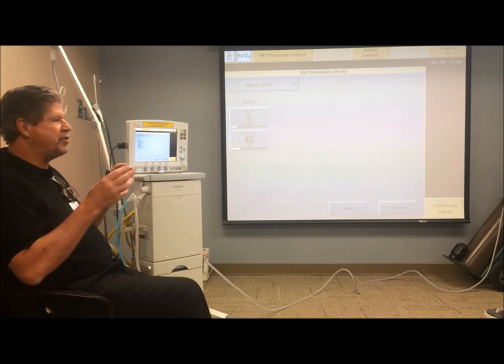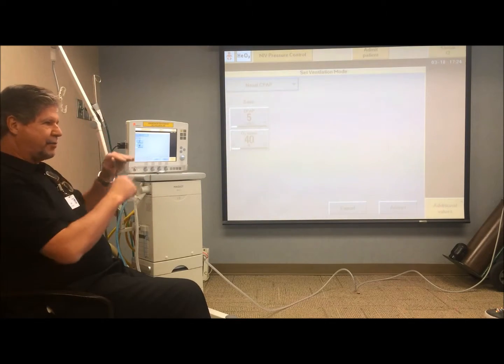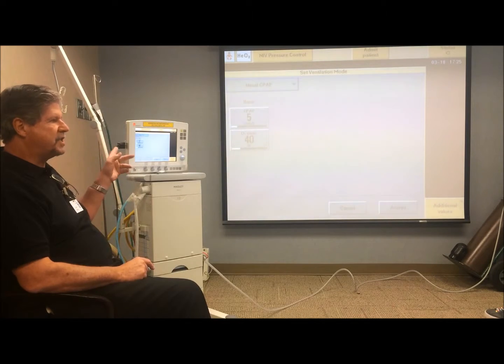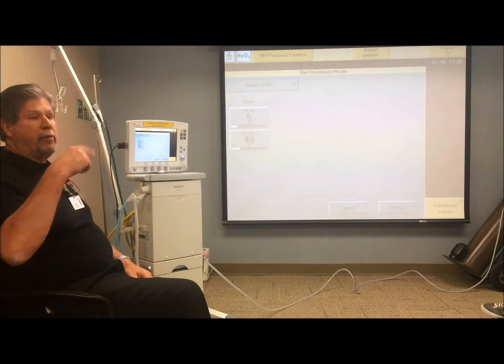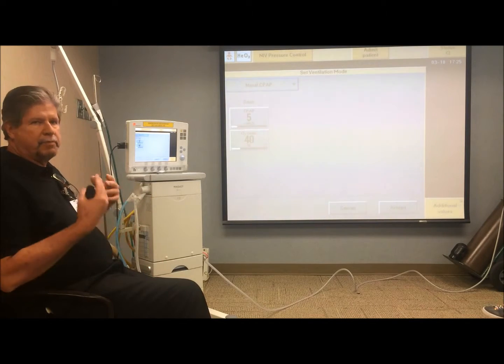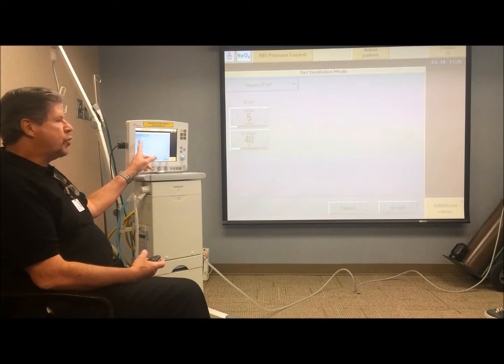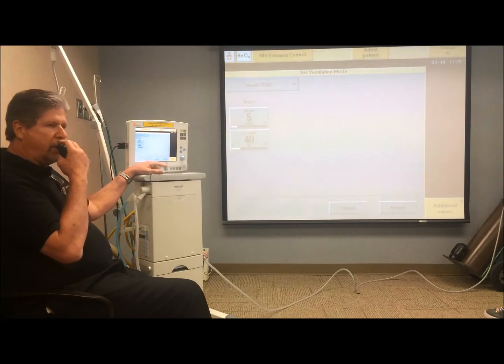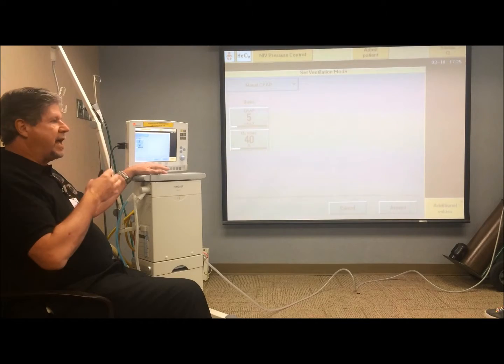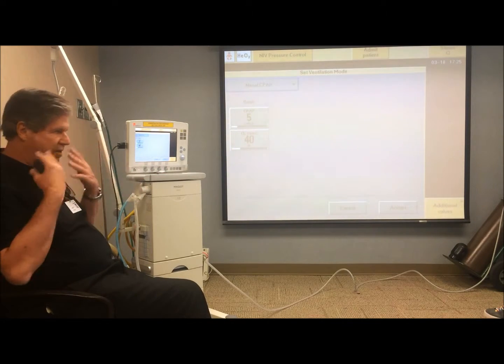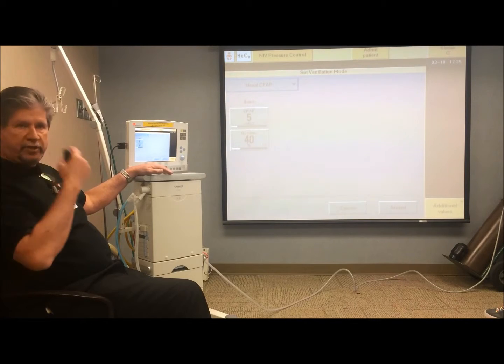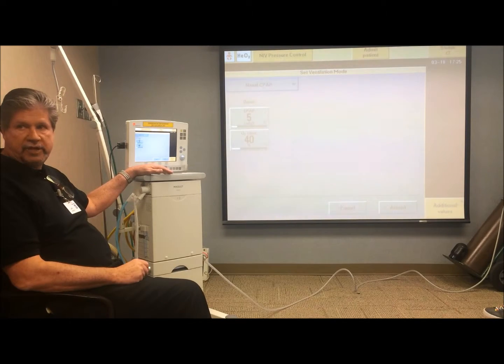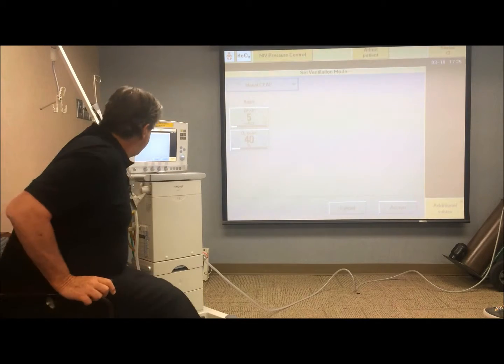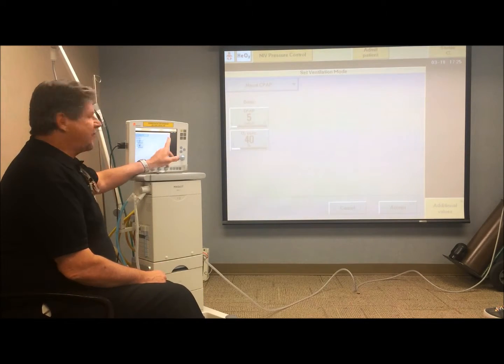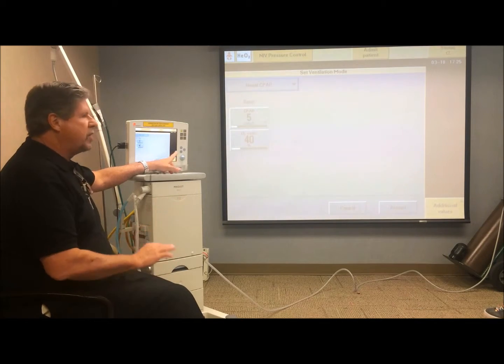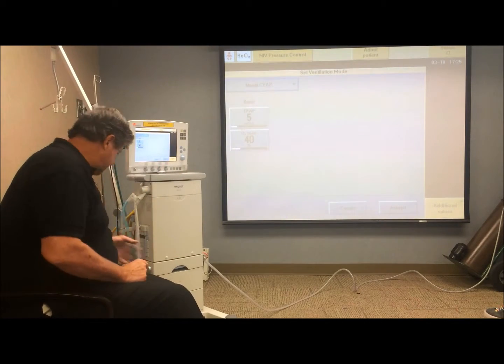It's pure CPAP as compared to using a device with a manometer and setting up a little PEEP column and all that. You know that you have an accurate CPAP level delivered. It's just that there's no bubble associated with it, so it can't be bubble CPAP. It's just plain CPAP, if you will. So this was specifically designed to use with prongs, not caring about leakage, and the babies don't have to trigger to get a flow. They will just breathe the flow that's running through the circuit, just like any other CPAP device. But the problem is, this would be great if it had a backup, right? This would be perfect.